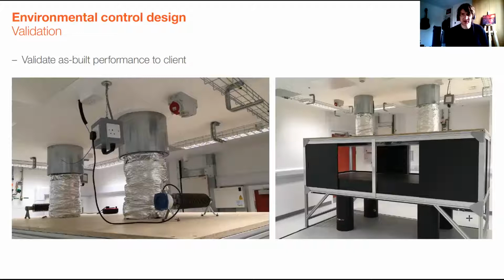One thing we did on this project that was different to normal projects is that, over and above the normal commissioning and testing done with the building empty, we simulated some in-use heat demands to prove the system could deal with real life conditions, before the department had moved in, so we had time to rectify anything found to be wrong.